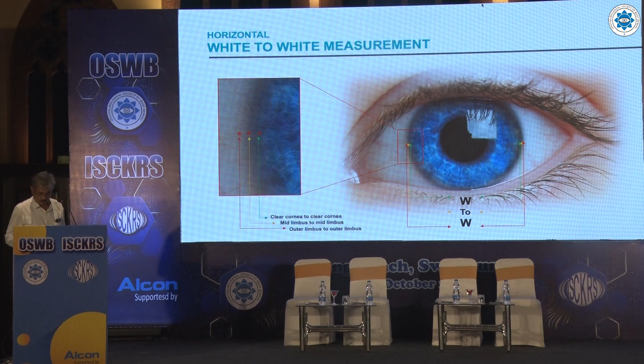And how ICL size matters. If the white to white is 11.46, 11.55, 11.62, and ACD is 2.9, the recommended size is 12.6, with no change in size across all these white to white values. But if ACD is more than 3.454, then you can see sizes of 12.1 and 12.6. So ACD and white to white combined determine what ICL size would be for a particular patient.